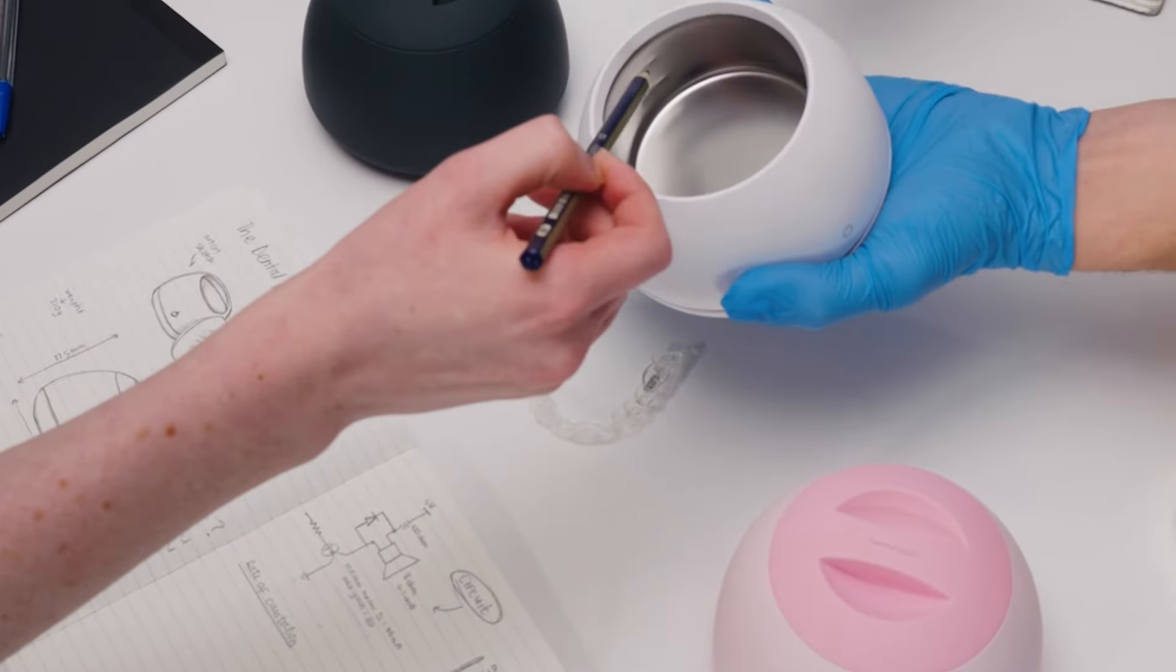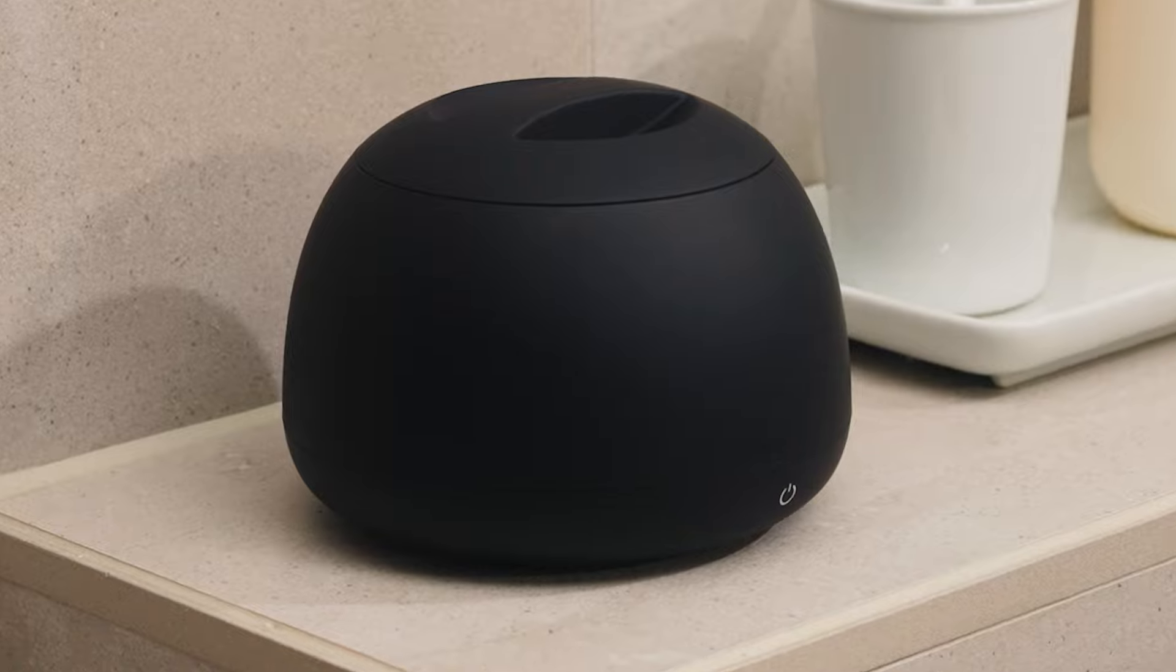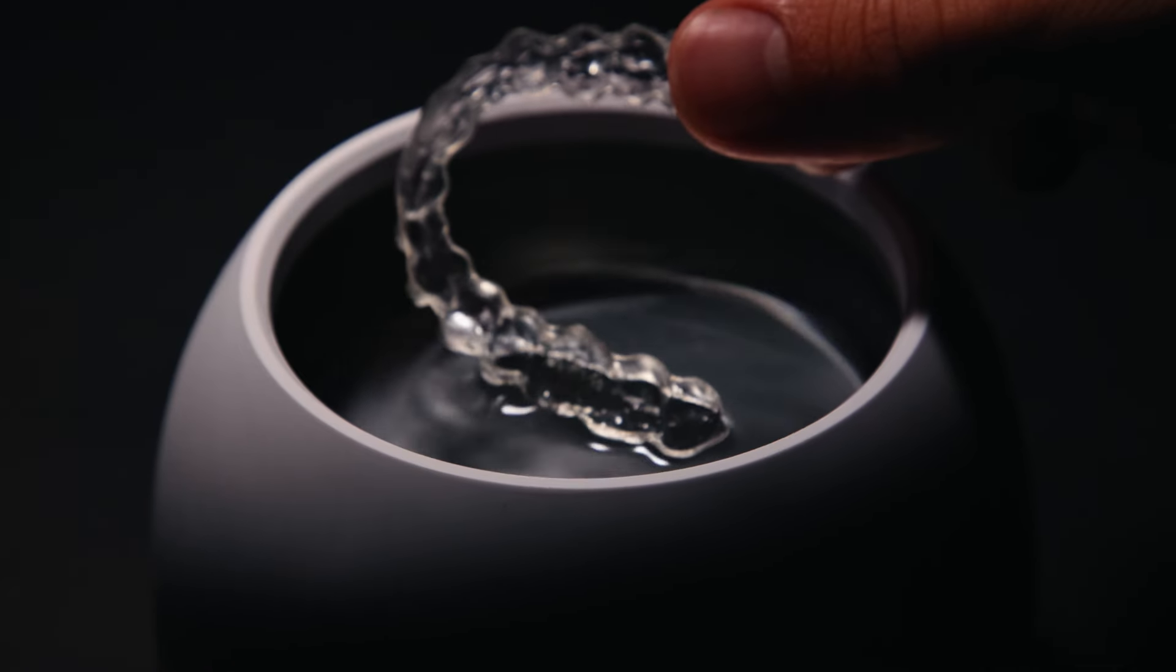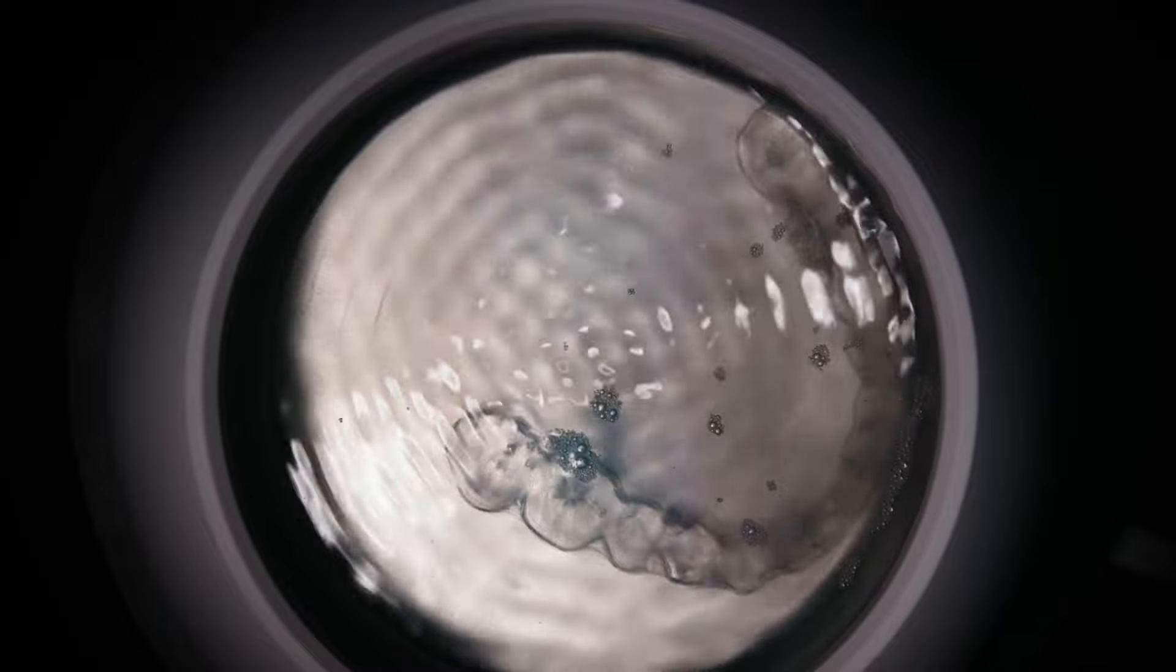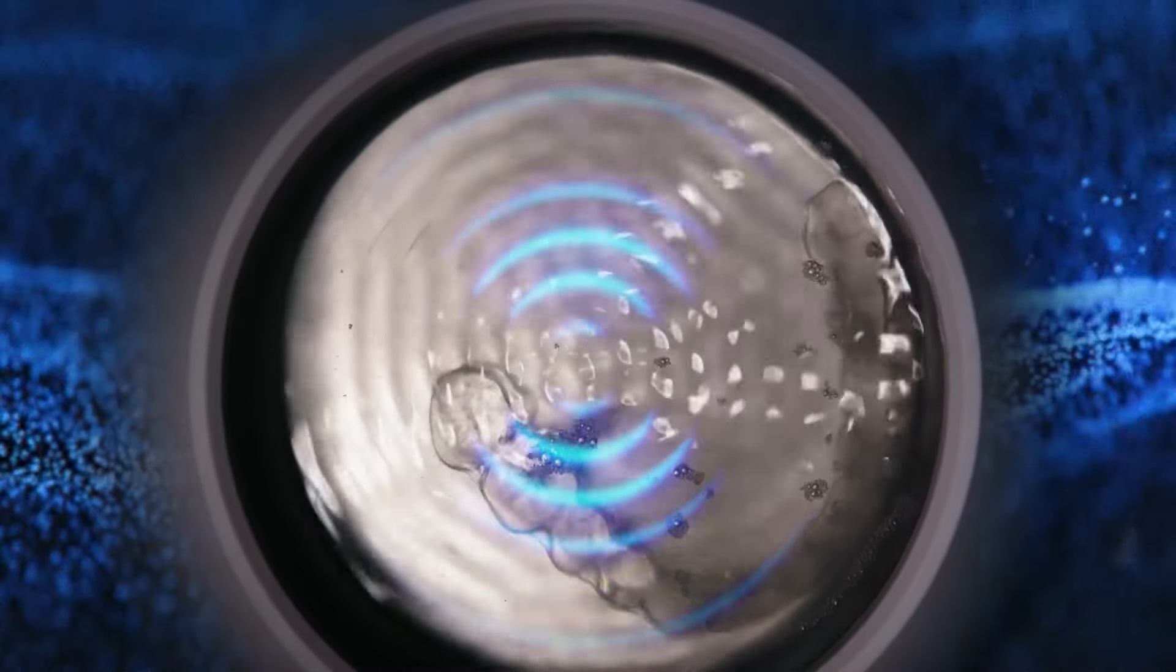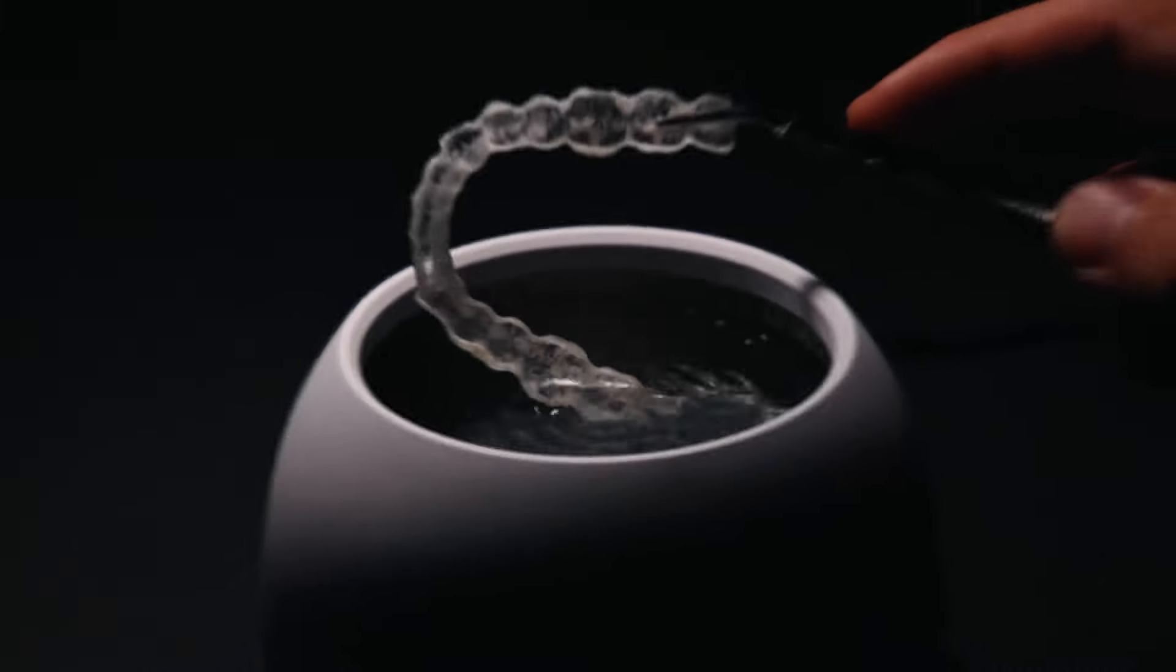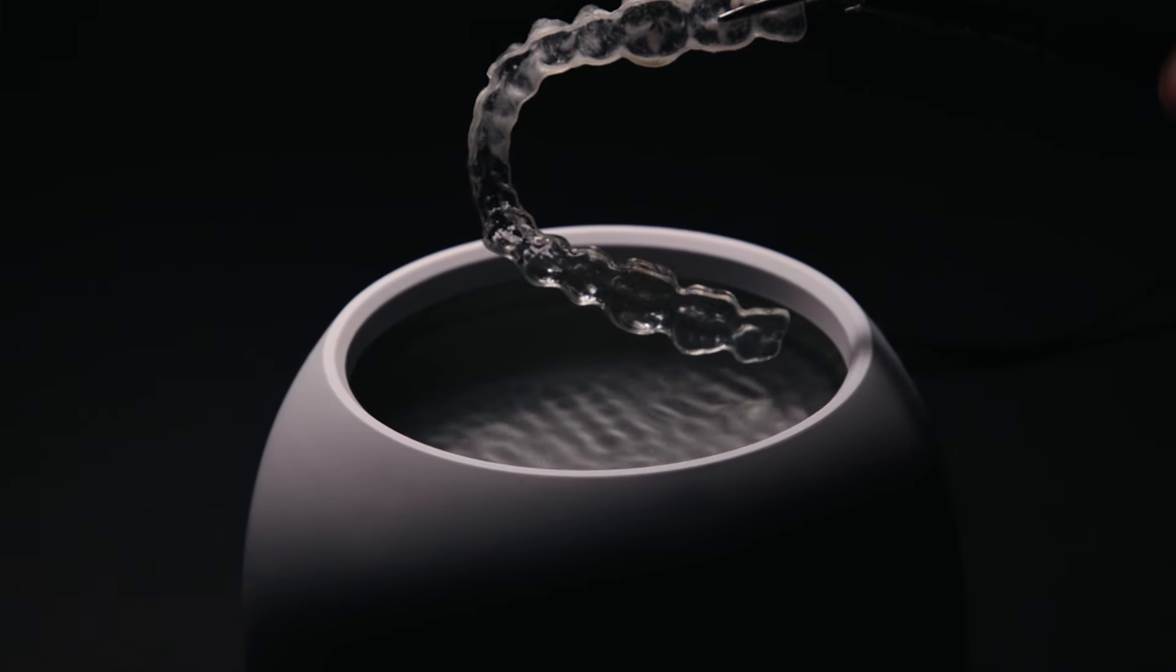Carefully developed over the last two years, the DentalPod Pro pushes the boundaries of ultrasonic cleaning technology. With innovative patented design and engineering, the DentalPod Pro has increased cleaning power using a dynamic frequency range of 42 to 45 thousand Hertz ultrasonic waves, while still being safe for all appliance types.